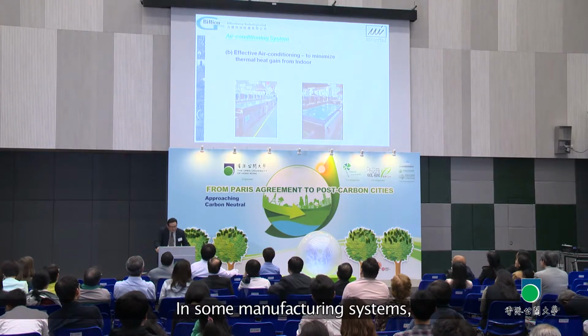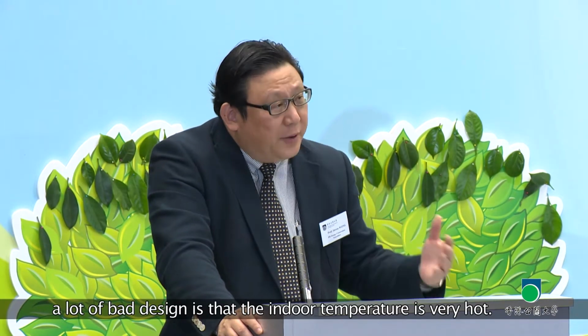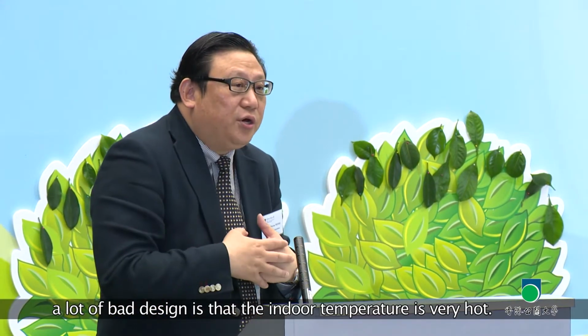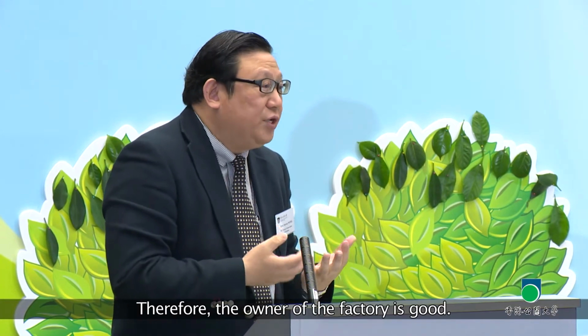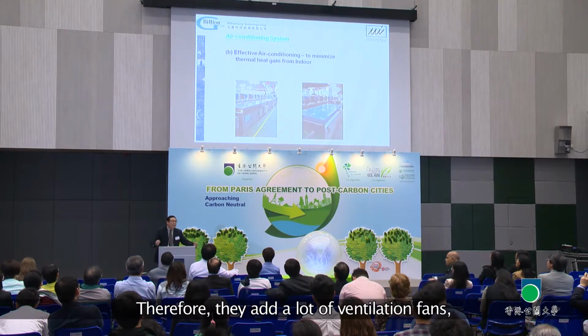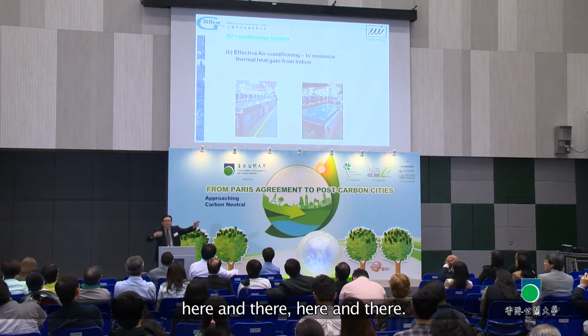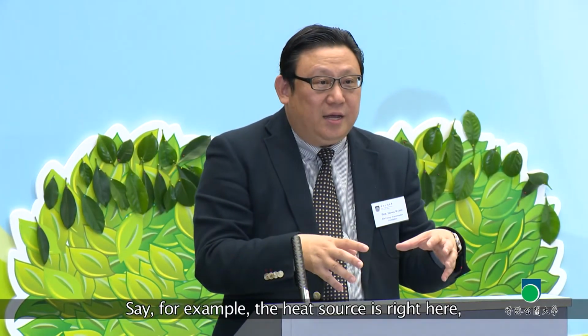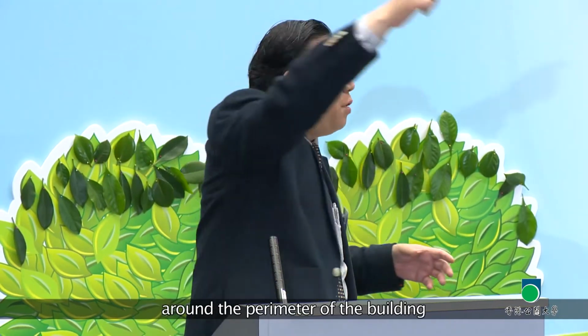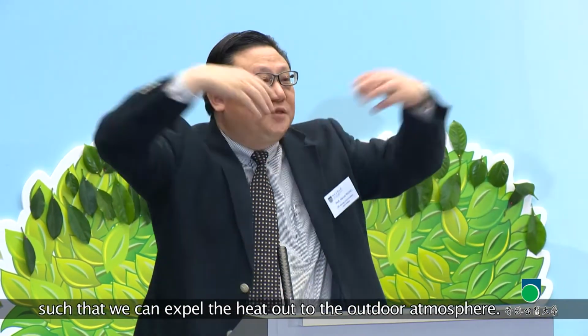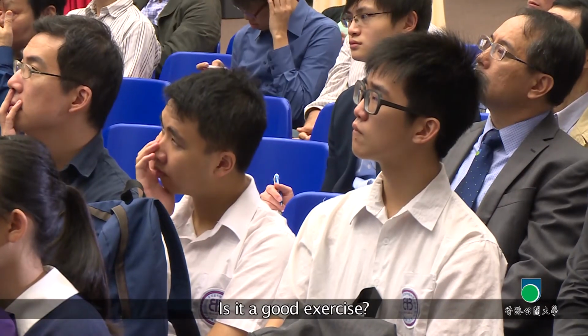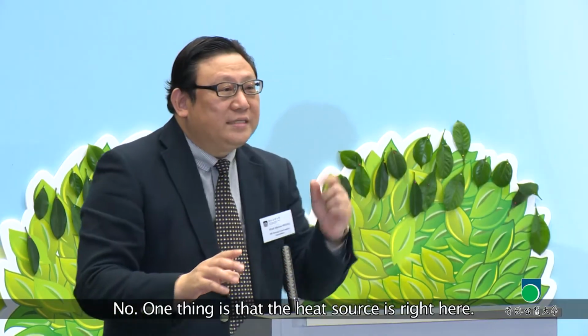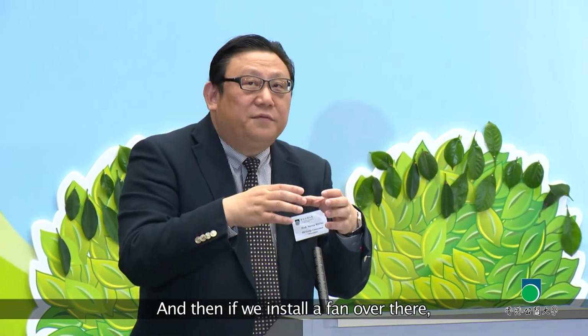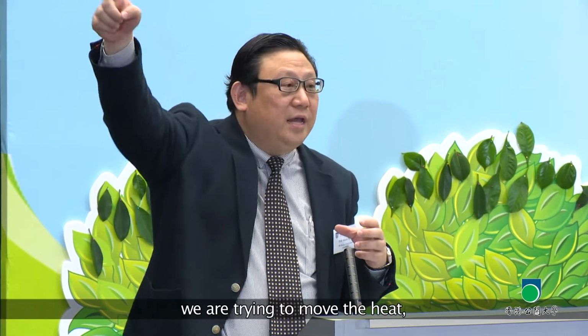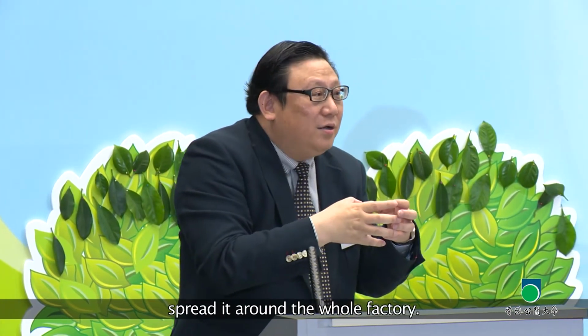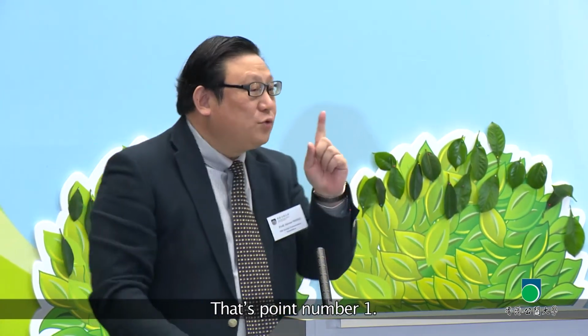In some manufacturing systems, a common bad design is that the indoor temperature is very hot. The factory owner, being considerate with the workers, adds many ventilation fans here and there around the perimeter of the building to expel the heat outdoors, even though the heat source is in one specific location. Is this good practice? No - if you install a fan elsewhere, you're just spreading the heat around the whole factory.